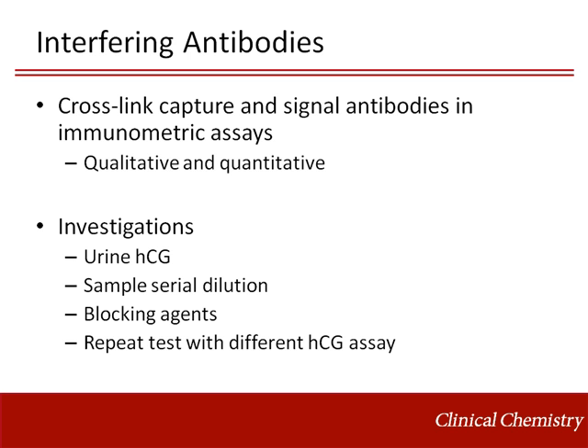Serial dilution of the sample can also be useful. Because interfering antibodies are reactive against the assay reagents and not HCG, samples that contain them may produce HCG results that deviate from the expected dose response. Blocking agents work by absorbing the interfering antibodies from the sample, thereby preventing their interference in immunoassays; however, their effectiveness depends on numerous variables including the interfering antibody class, specificity, and concentration. Repeating the test using a different HCG immunoassay — particularly one that utilizes antibodies produced from a different animal species — can be helpful as well.